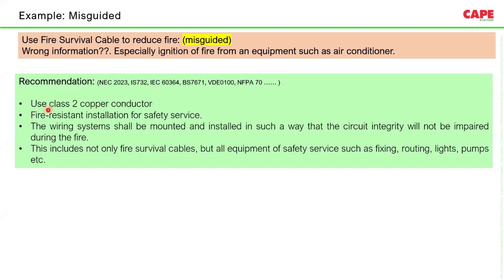So the recommendations in the standard, if we look, say you should use class 2 copper conductor. Fire resistant installation for safety services is mandatory. The wiring system shall be mounted and installed in such a way that circuit integrity will not be impaired during fire, and so on.